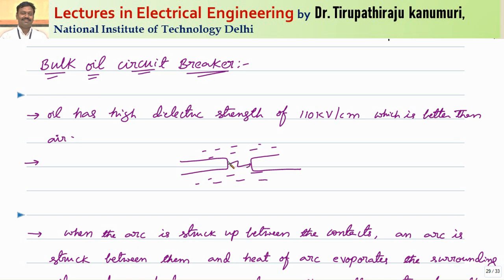The hydrogen gas will occupy a volume of nearly 1000 times that of the oil that is decomposed — if one ml is decomposed it becomes 1000 times in volume. That gas forms a bubble around the arc and the contacts. Because hydrogen gas is a very good conductor of heat, it provides a cooling effect on the arc, whereby recombination of charges happens and the dielectric strength of the medium is increased.